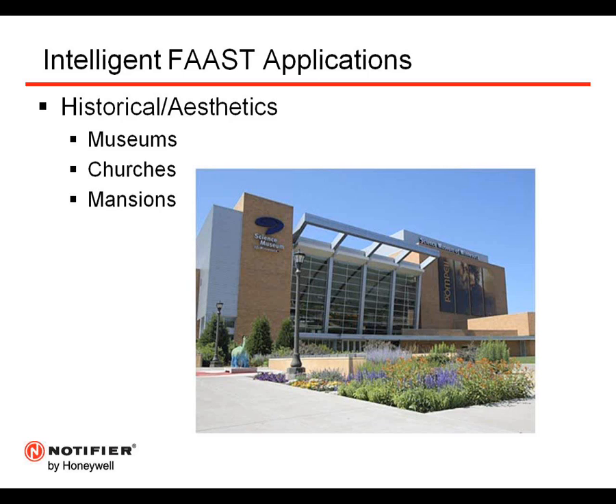They don't want to put spot detectors up on that space. So one of the other features of Intelligent FAAST Aspiration is that you can run the pipe network up maybe behind the wall or over the ceiling and then use capillaries that would come down from that hidden pipe network and go down into the protected space to be able to provide that true active smoke detection.